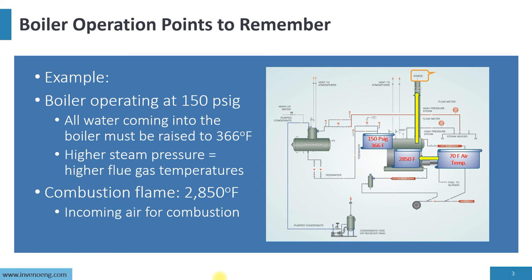The biggest loss in any boiler operation is flue gases going to atmosphere. It can be as much as 20% of your losses. So 20% of your fuel budget is going up the stack. So we have to be very critical of that loss.